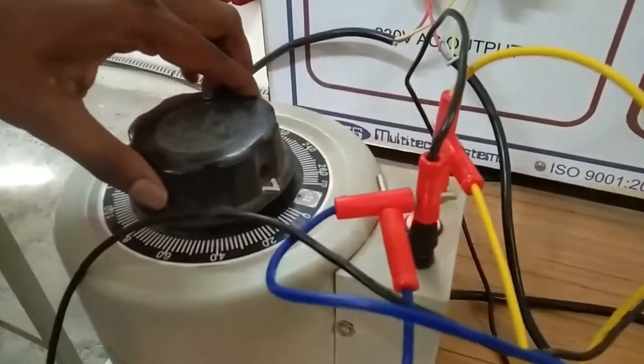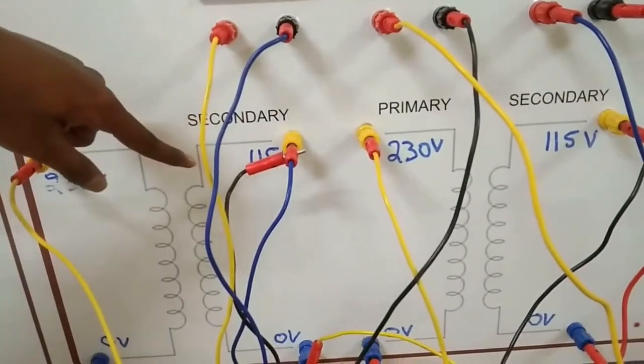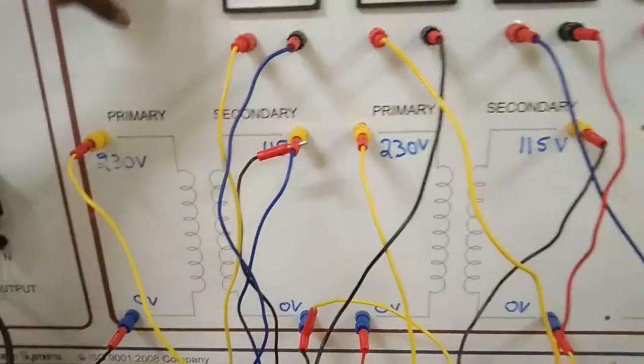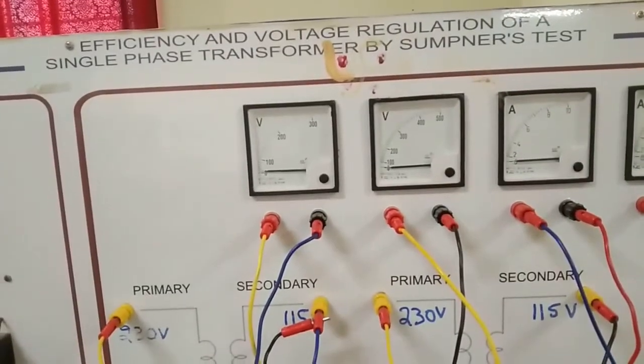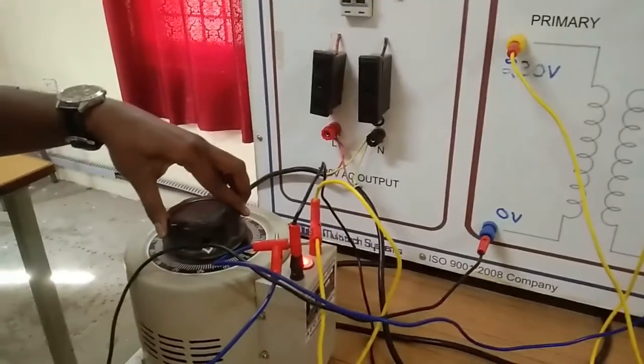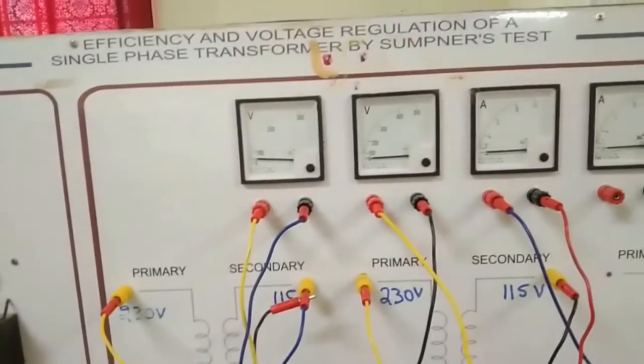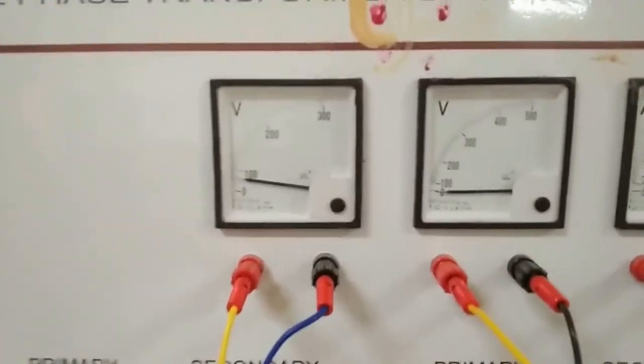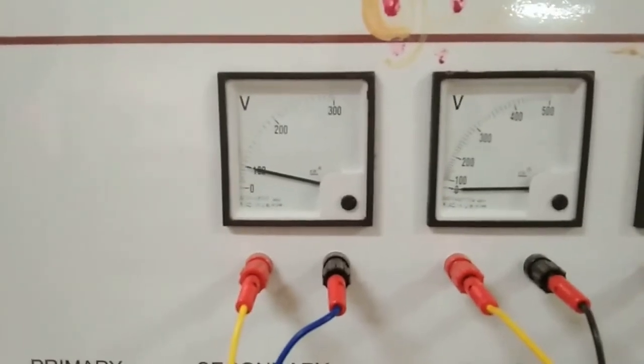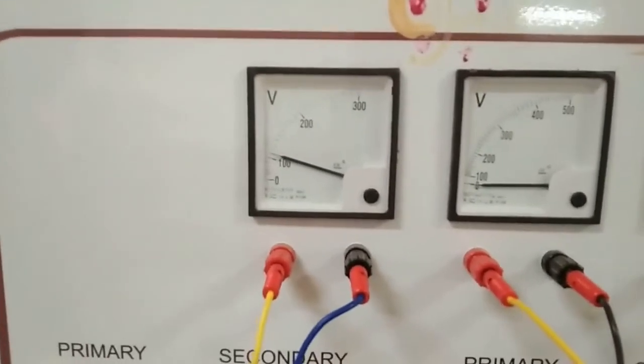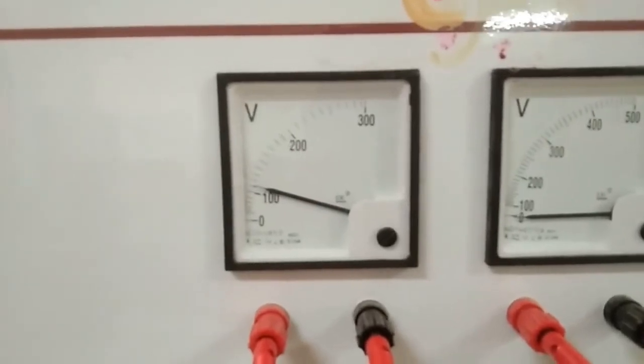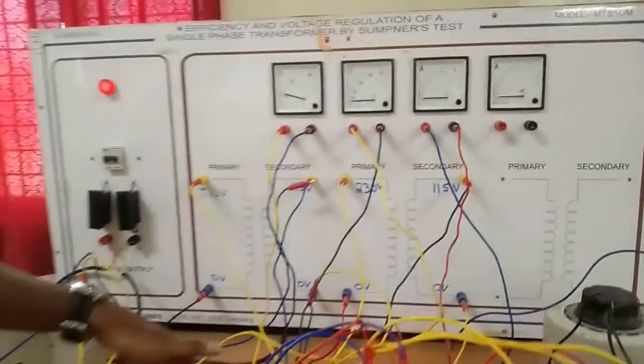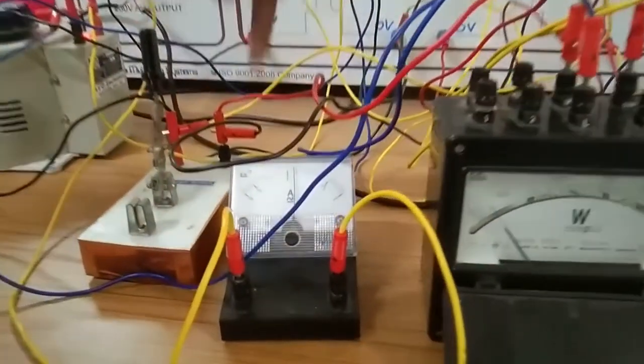How much? I have taken the primary as 115 volts. So I need to apply the rated voltage, right? So 115 volts I need to apply. That voltage will be displayed by this voltmeter. So just observe that voltmeter. The voltmeter has to indicate 115 volts, right? So 110 and 115 volts. Now after reading that 115 volts, we need to observe the primary current. This ammeter will display the primary current and this wattmeter will show the iron losses of both the transformers, right?